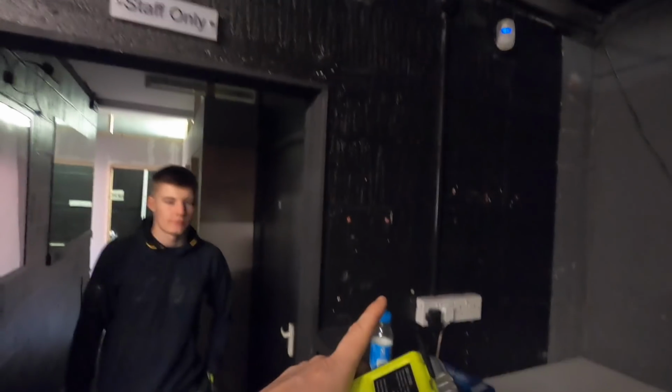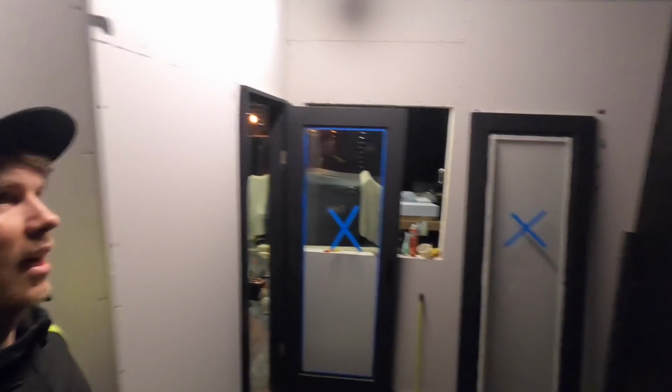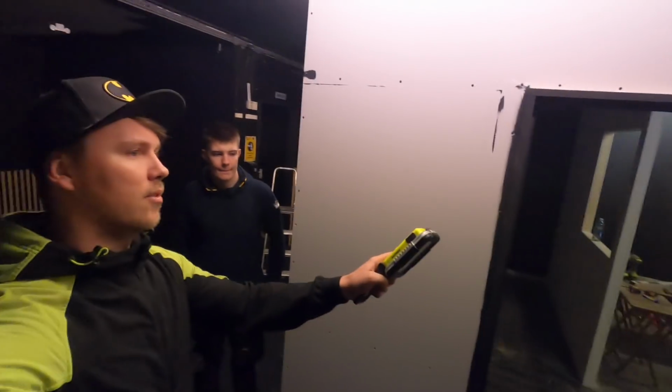The upstairs is a ring, but full well knowing once this has been done back in the day, through here, it's a very dark corridor, the ring sort of ends here. There's a junction box, and then there's been sockets tapped on and tapped on and tapped on years ago. So this is why it's having a bit of a revamp now to figure it out. Another socket up there is tapped on. 99% sure this here isn't on the ring.